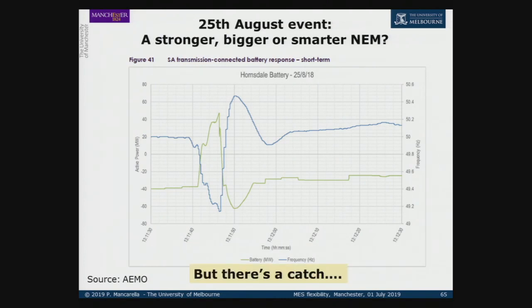What's the problem? What's the catch? The catch is that it was exactly this very fast response that caused the interconnector to trip. Because in a world where you'd associate a very fast change in power flows with a very fast change in angles - we all studied power systems, active power depends on the angles - if the protection on the interconnector sees a very fast change in power flows, it will think the angles are changing, therefore rotor angle instability. Because the protection doesn't know there is now a DC injection that can be faster than anything ever seen. So the protection thought the system was going into rotor angle instability, when actually it wasn't. It was just this super fast battery helping the system recover from the previous event.